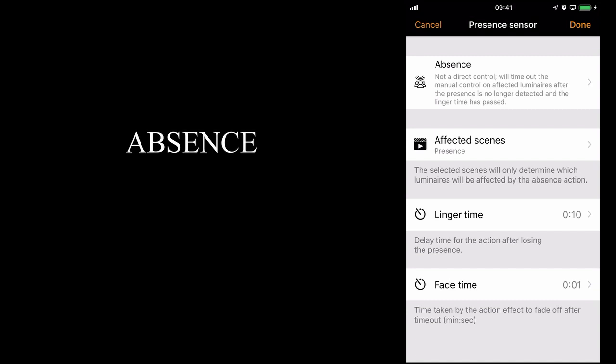What this actually means is, if somebody comes into a room, manually turns on the lights, the sensor will then wait until absence is detected. At that point it will check whether the linger time has passed or not, in this case 10 seconds. If the linger time has passed, and absence is detected, or no presence is detected, the sensor will then turn off the presence scene.